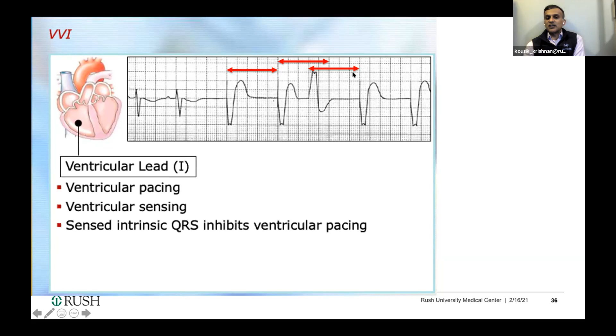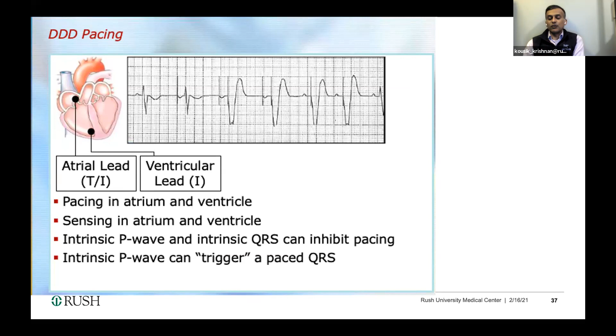DDD is a little more complex because you have two leads, and they're going to be working together. So the atrial lead will be sensing what's happening in the atrium. The ventricular lead will be sensing and pacing in the ventricle. DDD means it paces in both chambers, which is the first letter. It senses in both chambers, which is the second letter, and it can inhibit if there are intrinsic signals, or it can track if there's a sinus tachycardia or an atrial tachycardia. It can track that atrial rhythm in the ventricle.